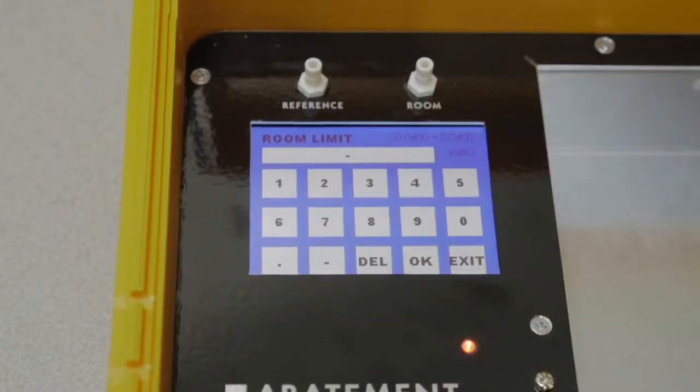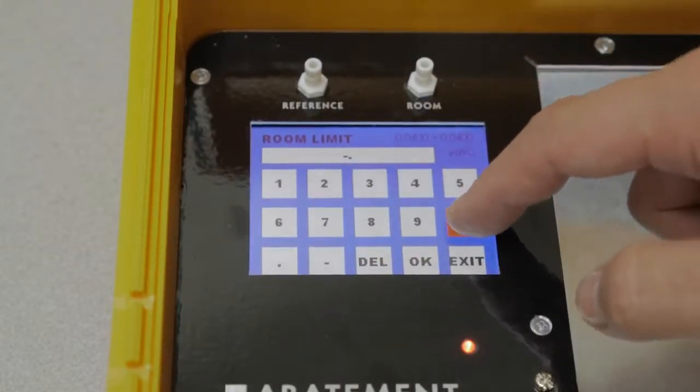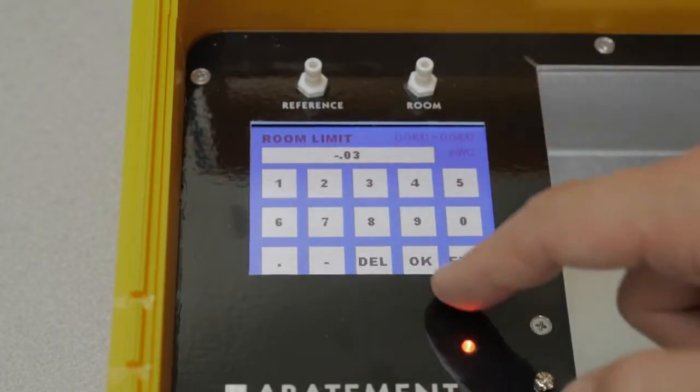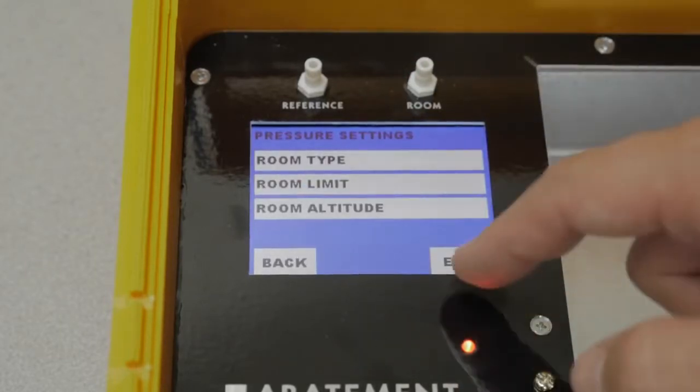If the room type is negative, anything above the set pressure limit will cause the system to alarm. If the room type is positive, anything below the set limit will cause the system to alarm.